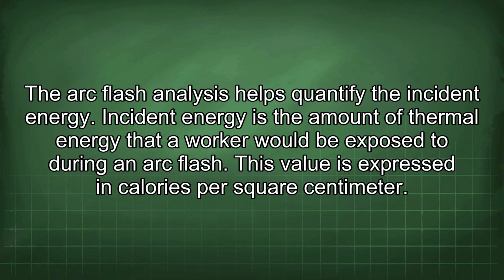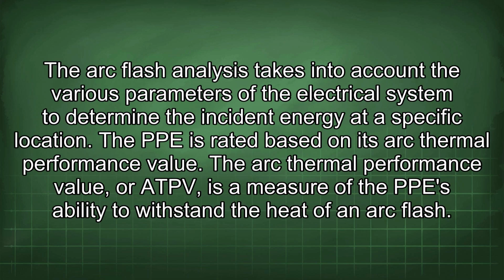The arc flash analysis helps quantify the incident energy. Incident energy is the amount of thermal energy that a worker would be exposed to during an arc flash. This value is expressed in calories per square centimeter. The arc flash analysis takes into account the various parameters of the electrical system to determine the incident energy at a specific location.